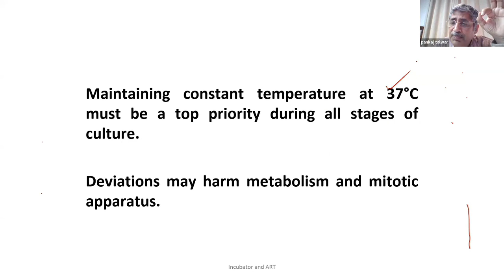So, sensors in the incubators. How many types of sensors are in the incubator? We have a sensor for temperature, a sensor for CO2, and a sensor for oxygen. I won't go into the details due to paucity of time, because class was also hacked for some time. But we need a temperature sensor in the incubator which will tell us 37 degrees centigrade, carbon dioxide 6%, and then we can also have oxygen sensors in the incubator. Normally, we don't have any nitrogen sensors. We don't use them. So for temperature control, we have to maintain 37 degrees centigrade. Less than 37 or more than 37 can lead to mitotic spindle damage, which we have covered.